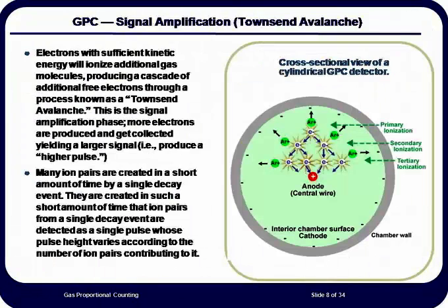The voltage gradient between the two electrodes will accelerate the ion pair towards their respective electrodes. If the electrons have sufficient kinetic energy, they can create additional ion pairs by collision with other gas atoms. Since the ionization of the first interactions will be multiplied, the total collected charge increases. The effect is known as the Townsend avalanche. The greater the number of primary events created by the original particle, the larger will be the total charge collected at the anode.